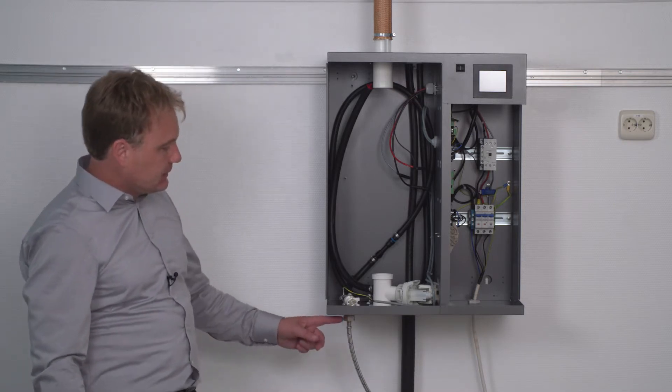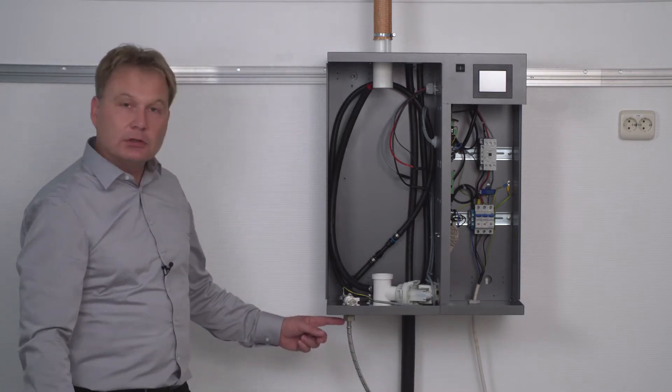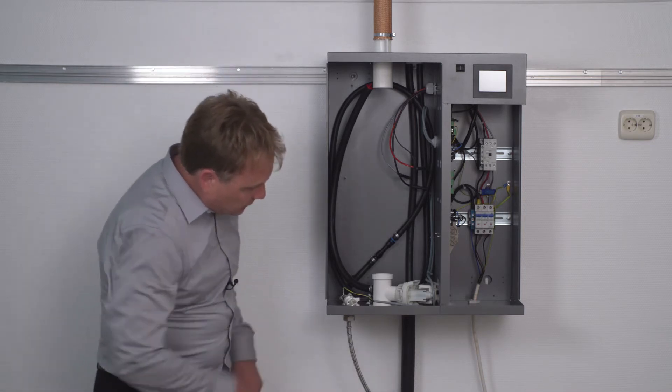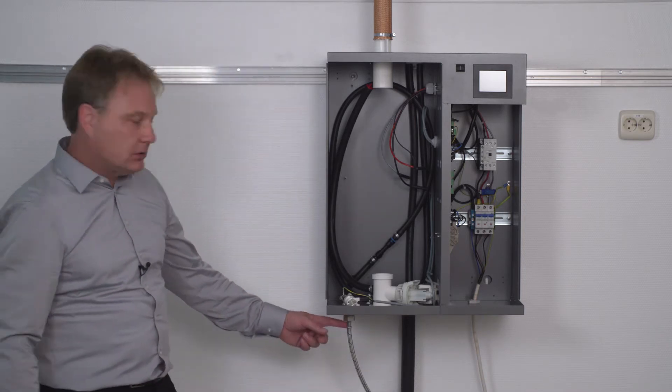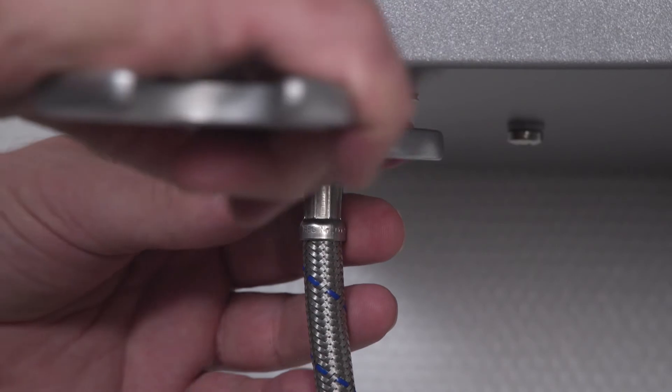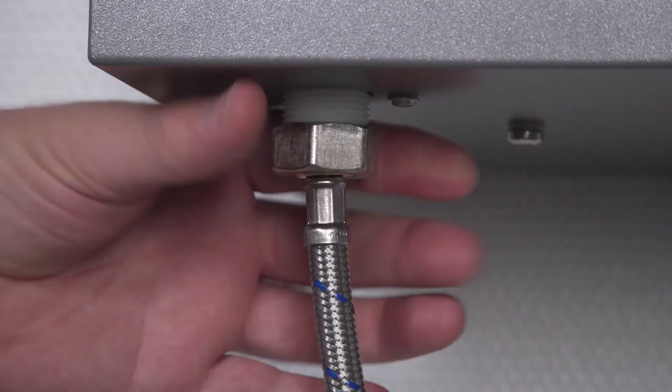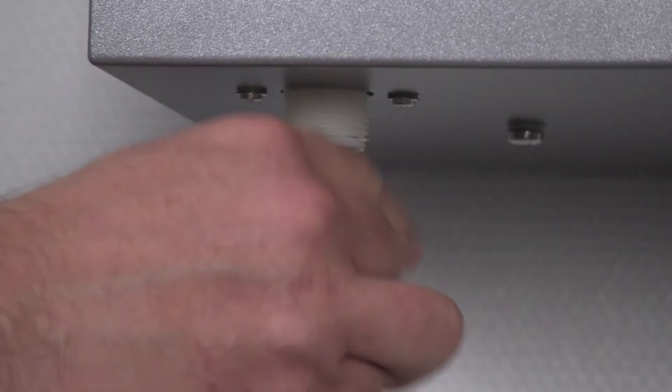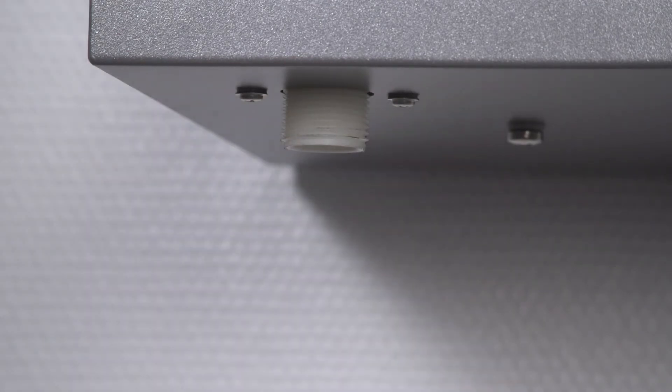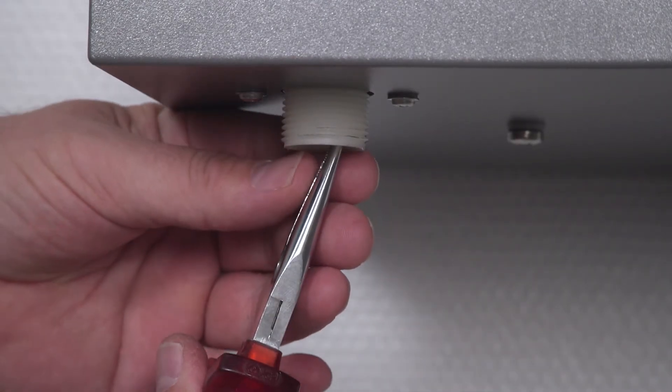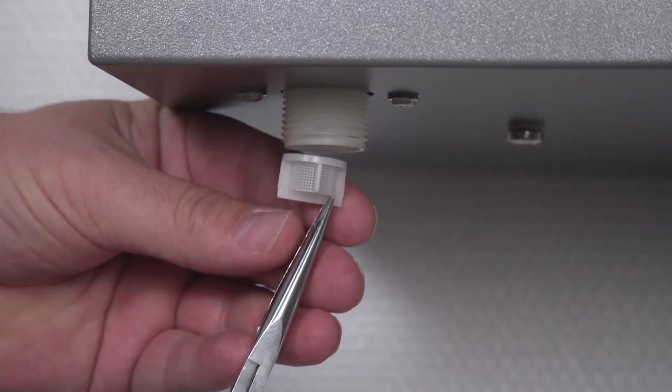Next, inspect the sieve at the tap water connection. Simply dismantle the water hose by loosening the nut and pull out the sieve with flat or pointed pliers. Clean the sieve under running water and then it can be reinserted.